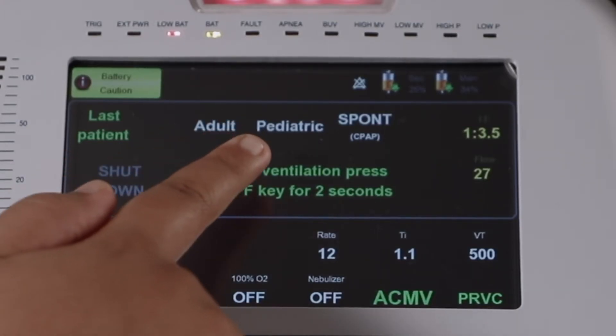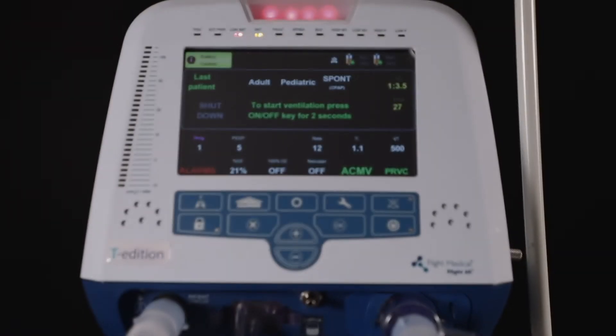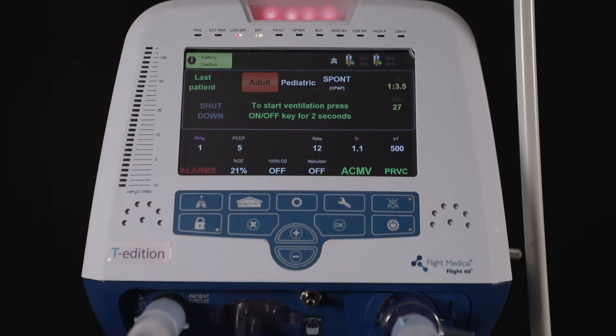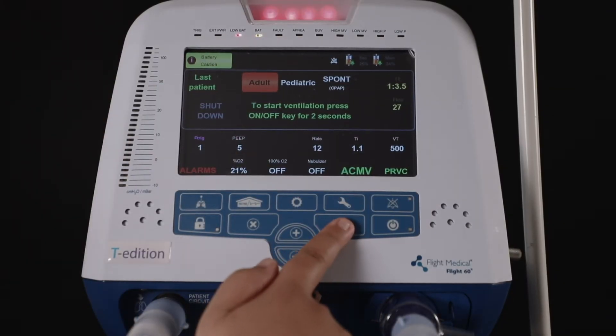Choose the type of patient — adult, pediatric, or SPONT. To select adult, press adult and press OK. A new alarm appears on the top left which says 'Check O2 Supply,' as the default setting of the ventilator for adult is 50% oxygen. Make sure to change the oxygen percentage to the patient's requirement.